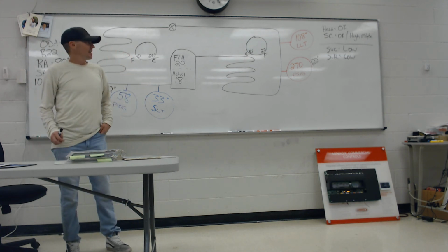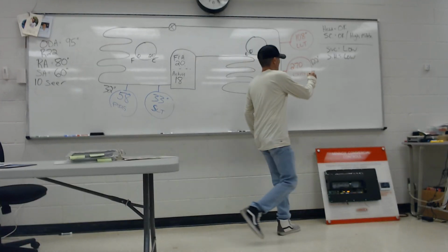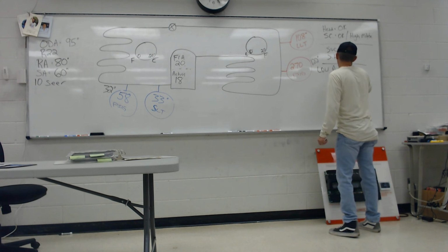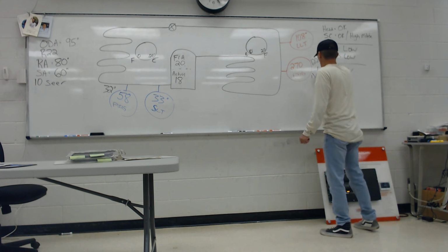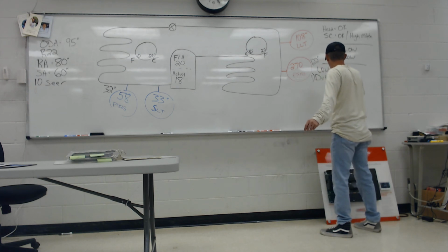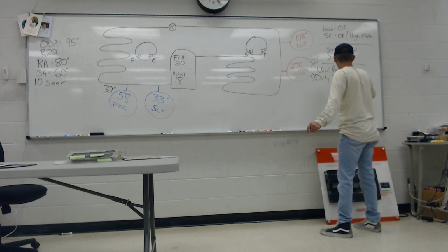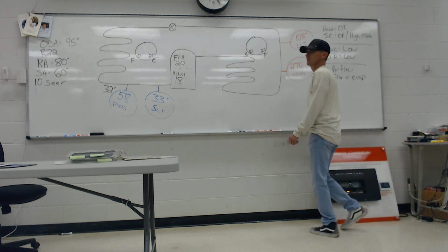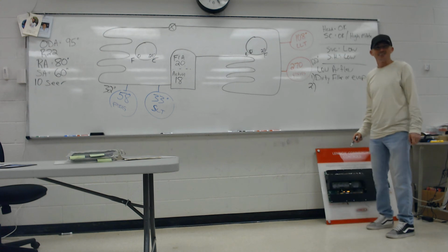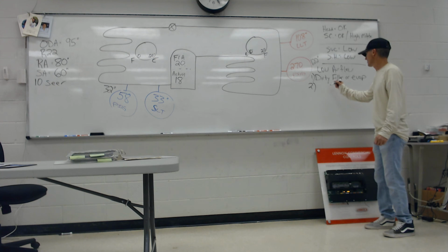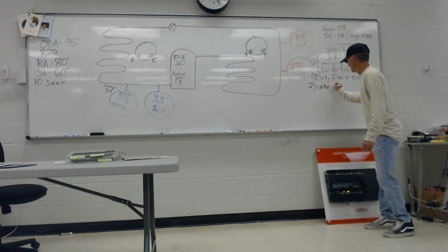We're going to run out of time, but real quickly, low airflow. Chet, what'd you say? Dirty filter or evaporator, yes sir. Undersized ductwork. Thank you. Have you guys ever seen any undersized ductwork? Yeah. You're damn right.